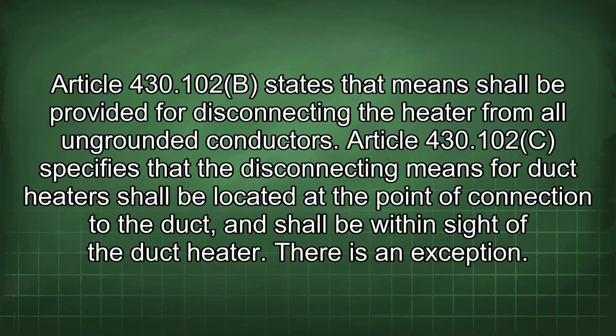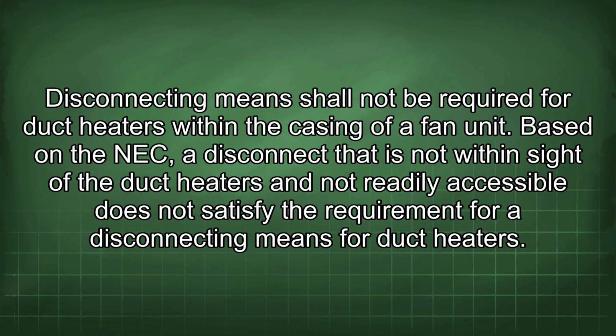430.102(b) states that means shall be provided for disconnecting the heater from all ungrounded conductors. 430.102(c) specifies that the disconnecting means for duct heaters shall be located at the point of connection to the duct and shall be within sight of the duct heater. There is an exception. Disconnecting means shall not be required for duct heaters within the casing of a fan unit.